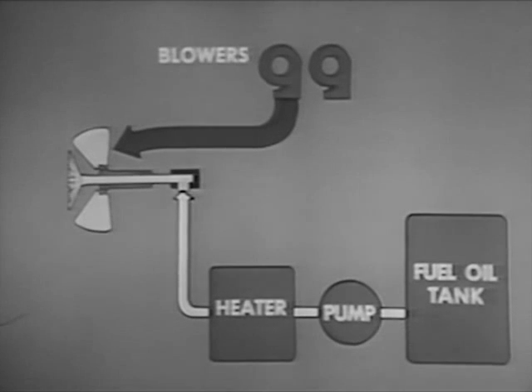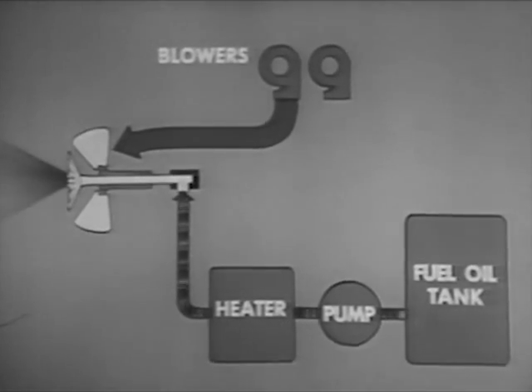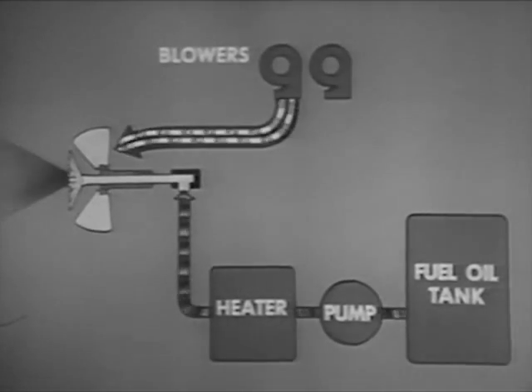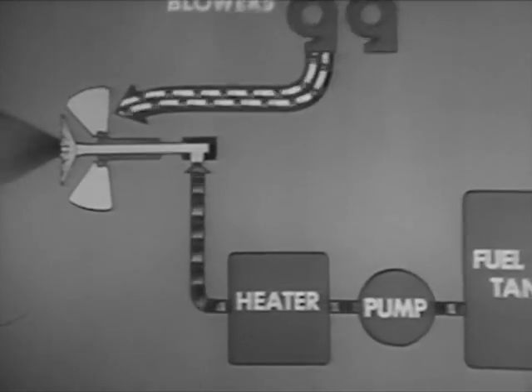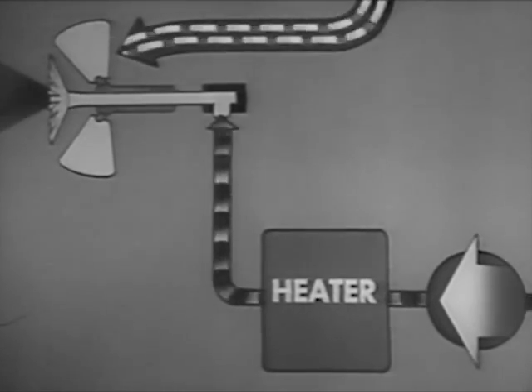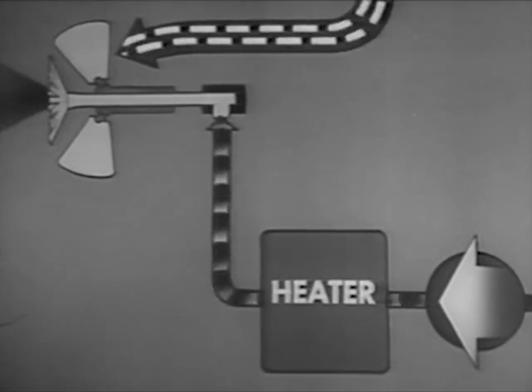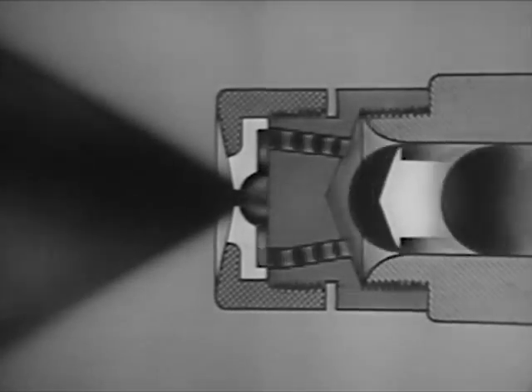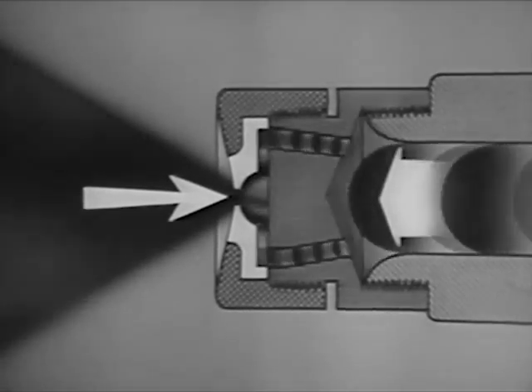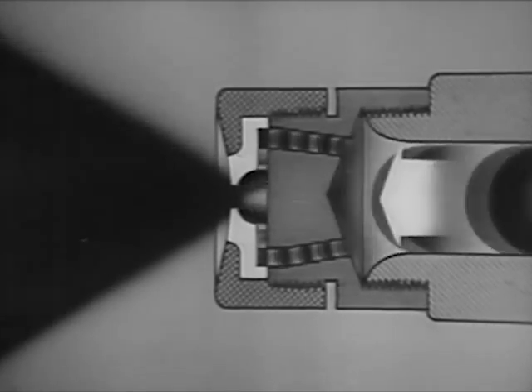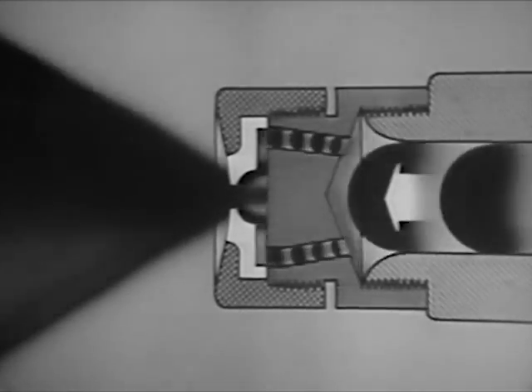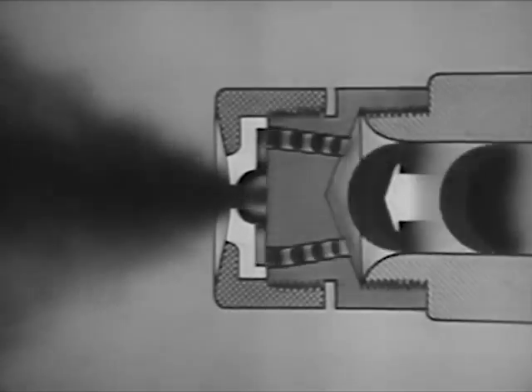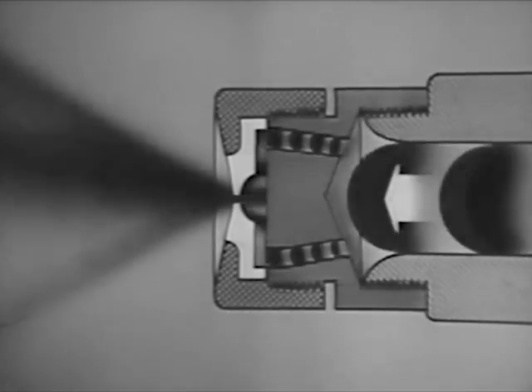You control the firing rate of the burner by varying the amount of fuel oil flowing through the burner. Of course, you must make corresponding changes in the amount of air reaching the burner when you change the amount of fuel oil. When you increase the pump pressure on the fuel oil line, you increase the quantity of oil going through the burner. When you decrease the pressure, you decrease the quantity of oil. However, when you want an increase in the firing rate, the sprayer plate in use at the time may have too small a capacity — that is, too small an opening — to provide the necessary quantity of oil, even with oil pressure at maximum. You must substitute a plate with a larger capacity. When you want a decreased firing rate, the sprayer plate's capacity may be too large to properly atomize the reduced quantity of oil. You must substitute a plate with a smaller capacity.